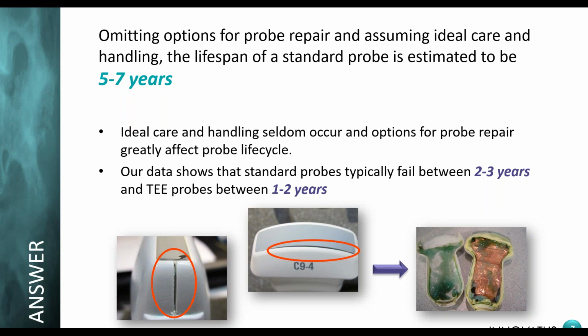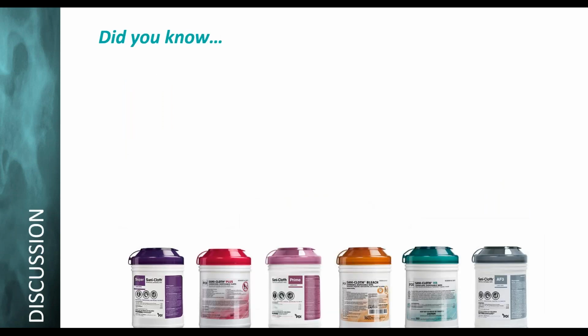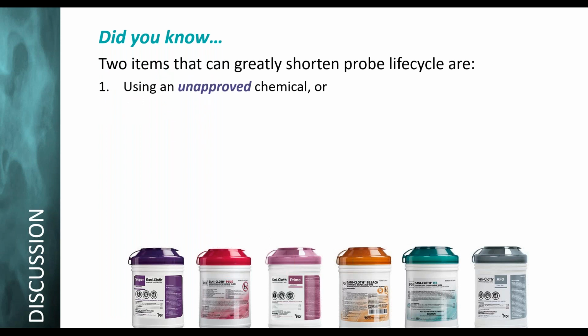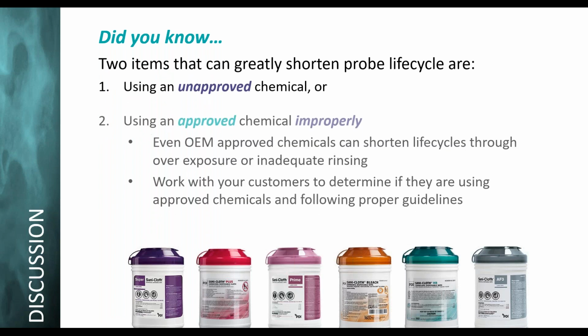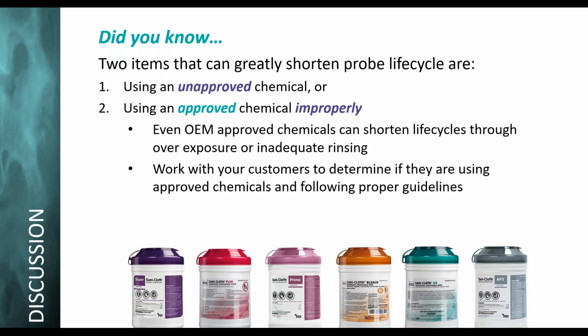And here's a little secret about the probe industry. Probes rarely die of natural causes. Something happened. And if they do die of natural causes, it's usually the wires go. And so 2 items that can greatly shorten probe life cycle are using an unapproved chemical or using an approved chemical improperly. When people get a Philips machine, a GE machine, Toshiba, whatever the flavor is, there's always a user manual. It tells you what chemicals you can use on a transducer. You have to follow that because if you don't, you will damage that transducer.